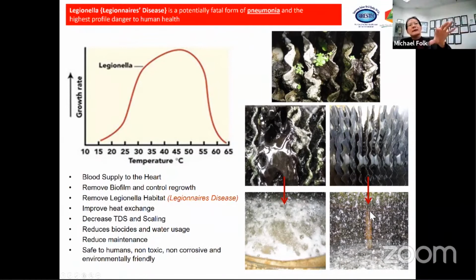So this is when the infill of the cooling tower is doing what it's supposed to do, and it's optimizing the efficiency. What it does is remove the Legionella habitat, remove biofilms, control regrowth, improve heat exchange, decrease TDS and scaling, reduce biocides and water usage, reduce maintenance, and it's safe to humans. It's non-toxic, non-corrosive, and environmentally friendly.